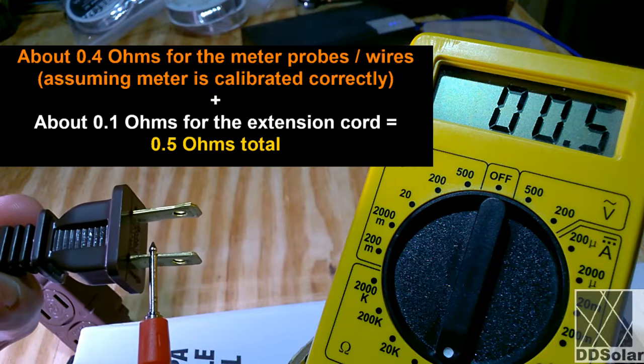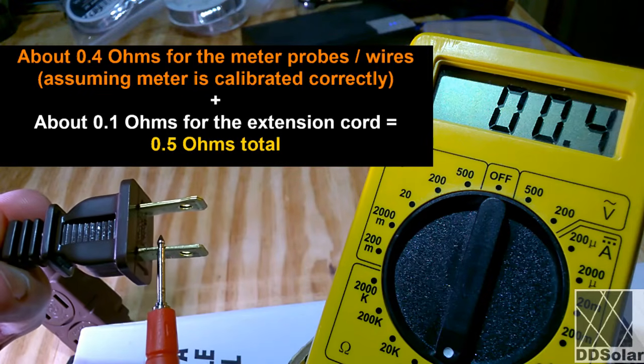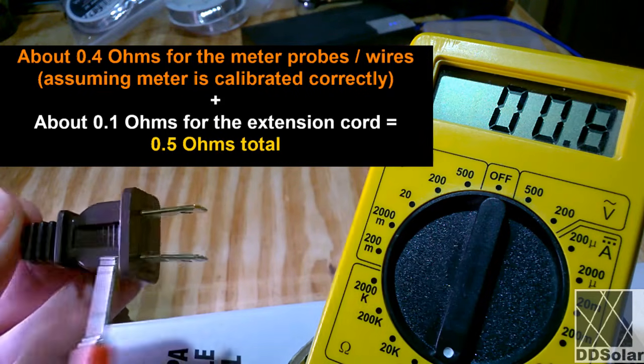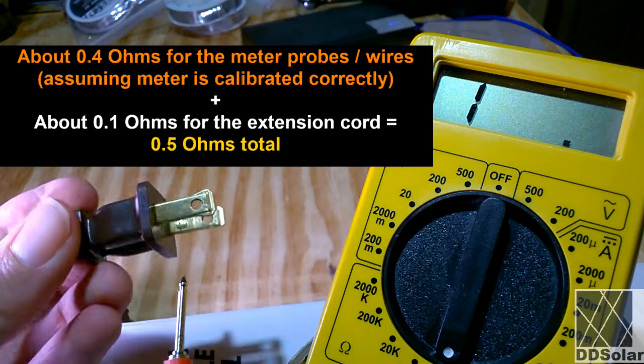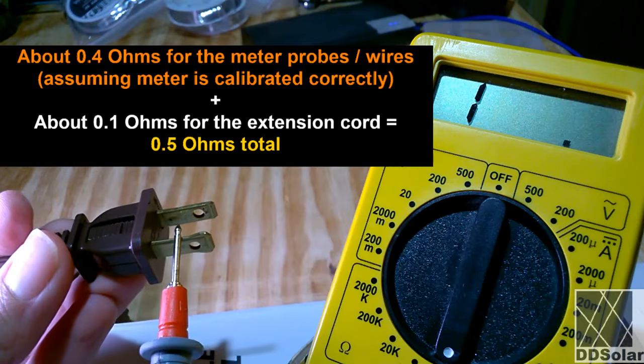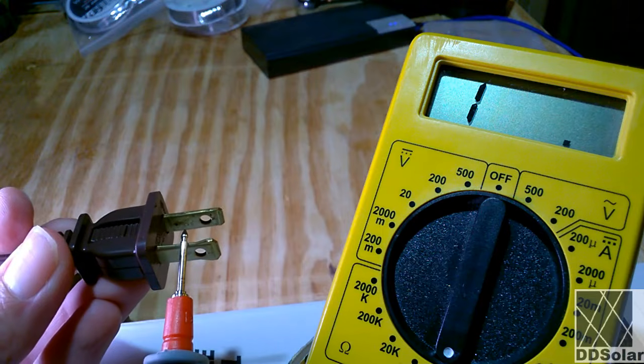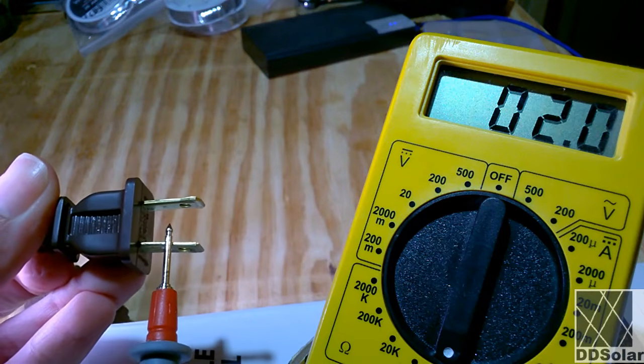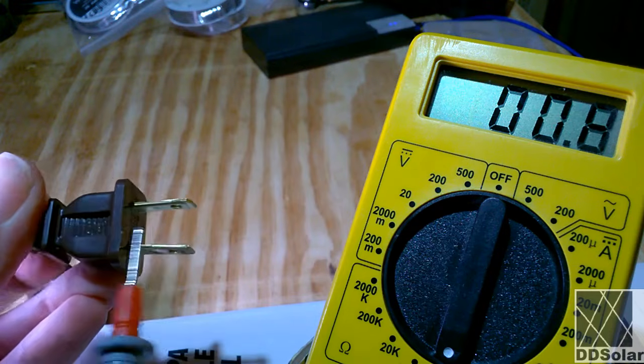And what I'm seeing here is about 0.5. So really, this cord has about 1/10 of an ohm of resistance. Now, what I shouldn't see, if I turn the cord around and touch the other side, I shouldn't get anything. And the reason is I'm not connected to that side. Now, if you want to test a bad extension cord using what's called a continuity check, you can actually see which side you're connected to and which side still has an intact functioning wire inside.